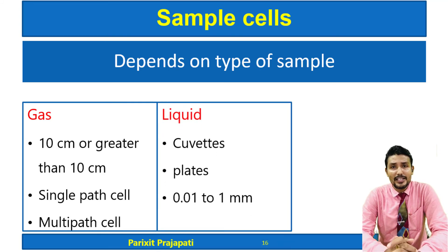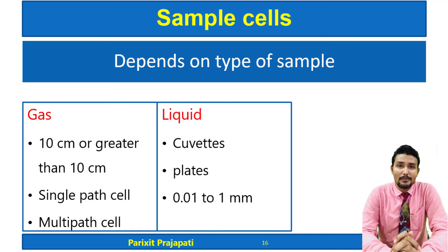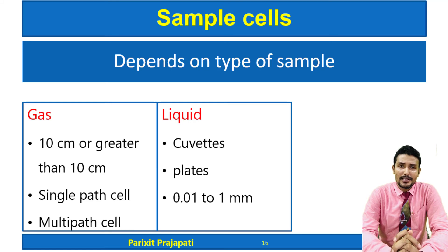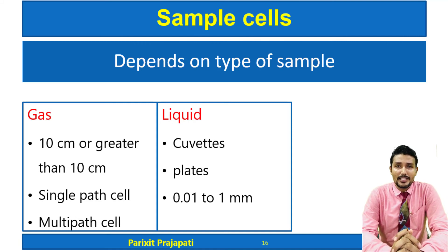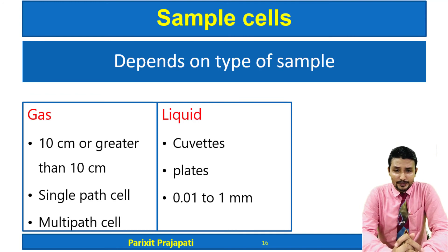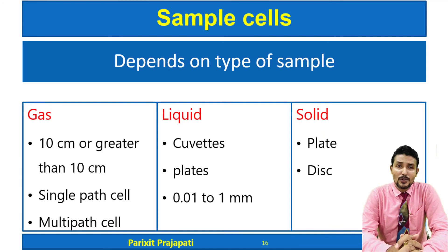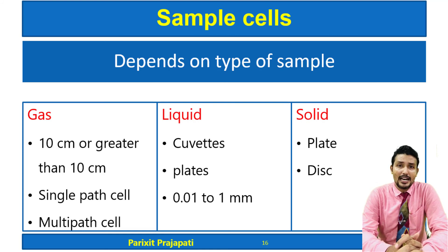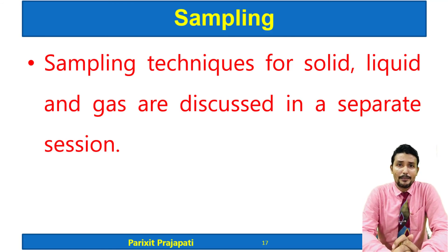For liquid or solution samples, cuvettes and plates with a thickness of 0.01 to 1 mm are used. Nowadays very compact sample cells are used with the advancement of technology, which will be discussed in a session on instrumentation advancements. For solid samples, the material can be placed between plates or in a disk. Since sampling is a very important part of recording IR spectra and involves many types of samples — liquids, solids, and semi-solids — a dedicated separate session covers this topic.